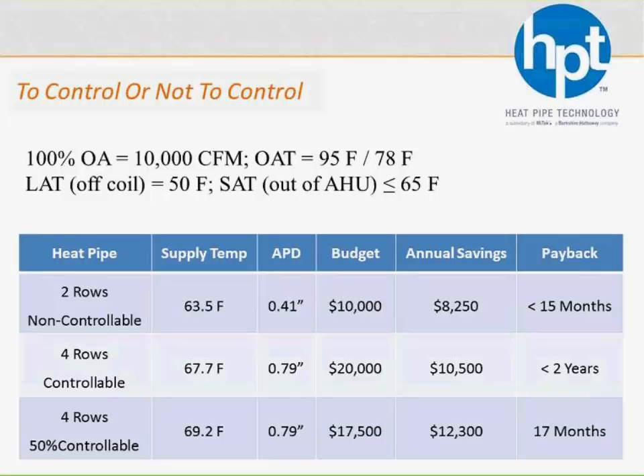So one thing you'll find is that when you do a controllable heat pipe, as soon as you add control valves to it, you do lose some performance because valves are essentially adding friction, so now that energy is not going towards reheat, it's going towards friction loss. So when you add half as many valves, you actually gain some performance. So instead of 17.7 degrees of reheat at design day, we're getting about 19 degrees of reheat. Throughout the year, there are fewer valves adding friction, so you're getting even better performance. You're adding the same statics, there's still 4 rows, but now there's half as many valves that you're paying for.